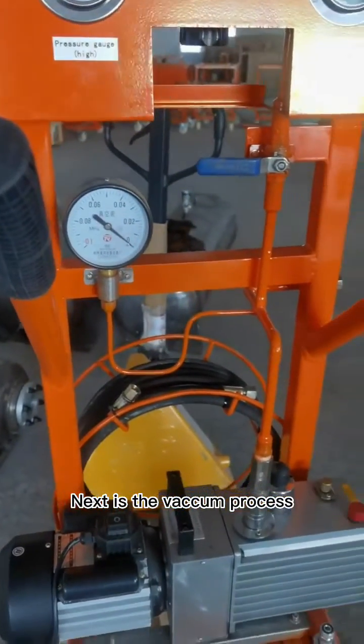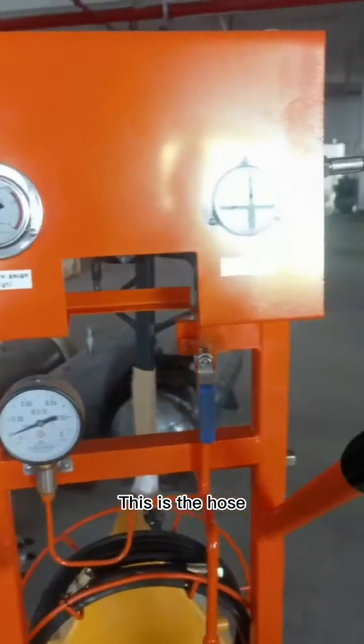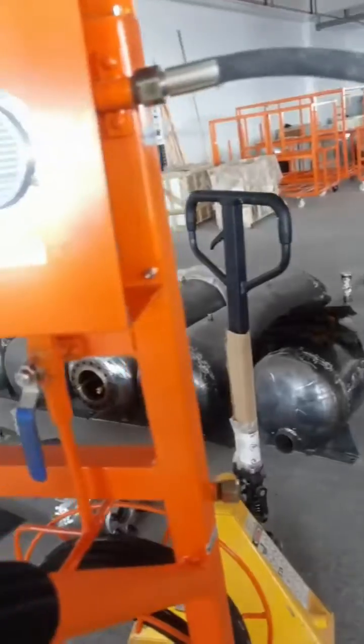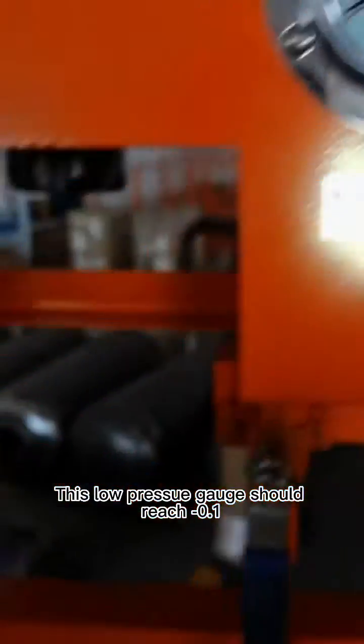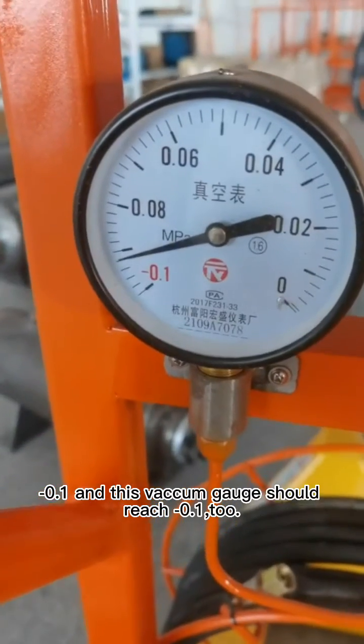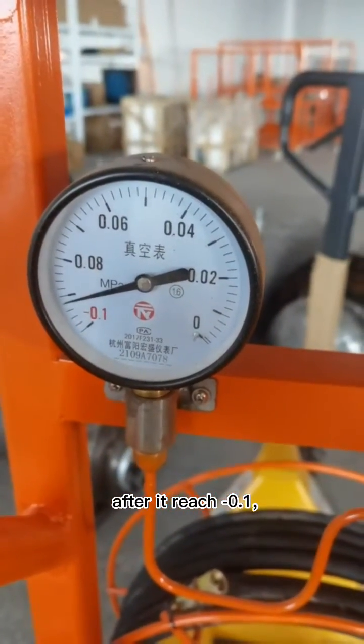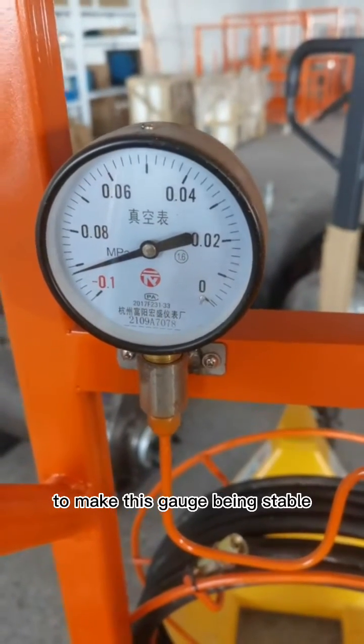Next is the vacuum process. This hose connects with the vacuum machine, and connects to the switchgear or small switch. This low pressure gauge should reach -0.1, and this vacuum gauge should also reach -0.1. After it reaches -0.1, let it run for a longer time to make the gauge stable.